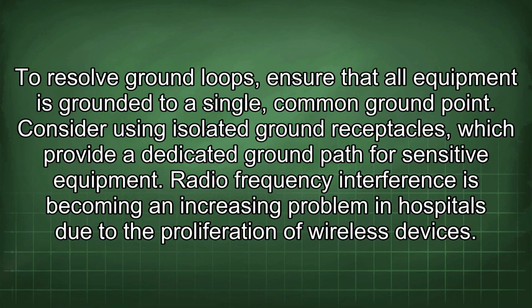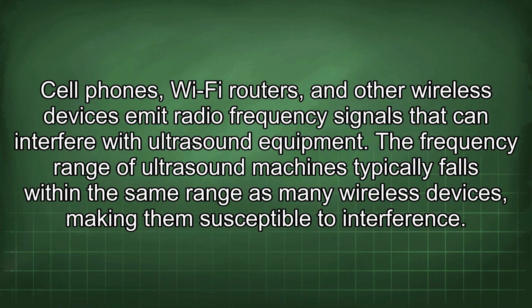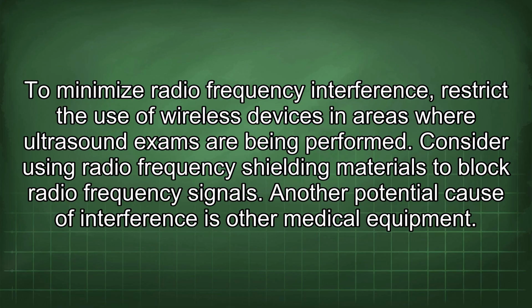Radio frequency interference is becoming an increasing problem in hospitals due to the proliferation of wireless devices. Cell phones, Wi-Fi routers, and other wireless devices emit radio frequency signals that can interfere with ultrasound equipment. The frequency range of ultrasound machines typically falls within the same range as many wireless devices, making them susceptible to interference. To minimize radio frequency interference, restrict the use of wireless devices in areas where ultrasound exams are being performed. Consider using radio frequency shielding materials to block radio frequency signals.